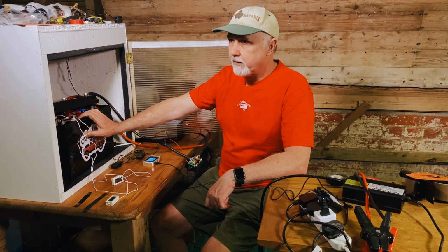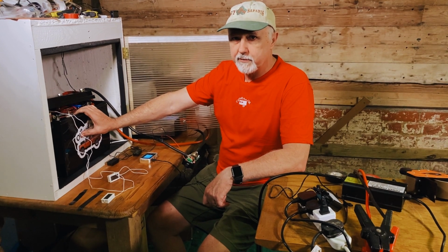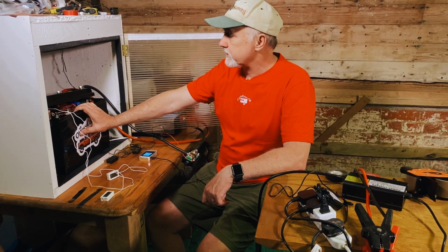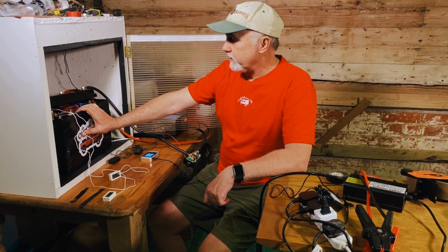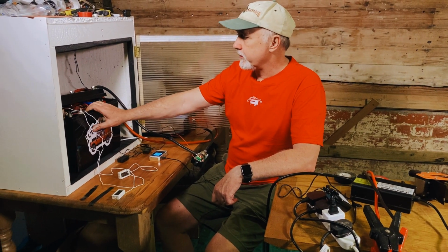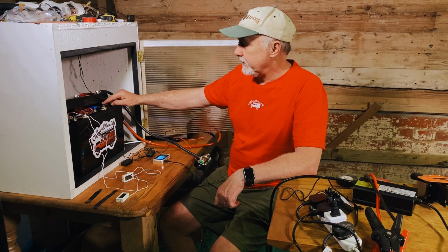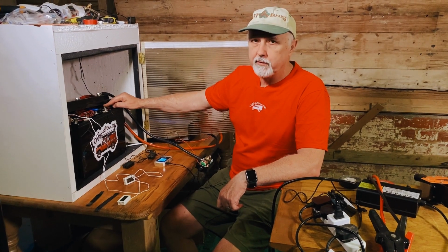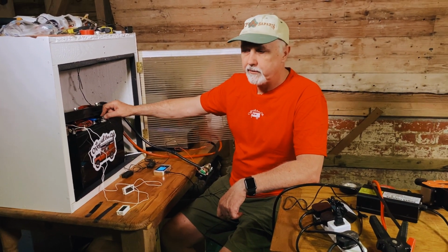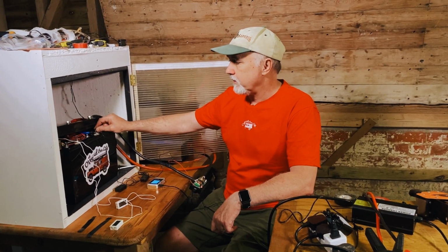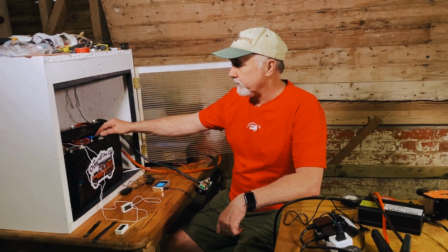It was absolutely fine. It got to about 45% state of charge, so used up 55% of its charge. And the hottest terminal was this negative one here, which got to about 60 degrees centigrade, so a 30 degree increase over 1 hour of very heavy load.